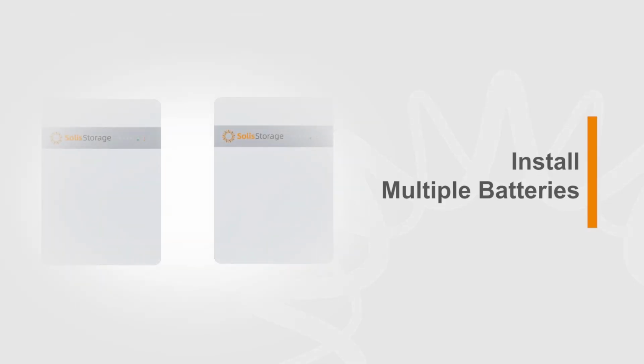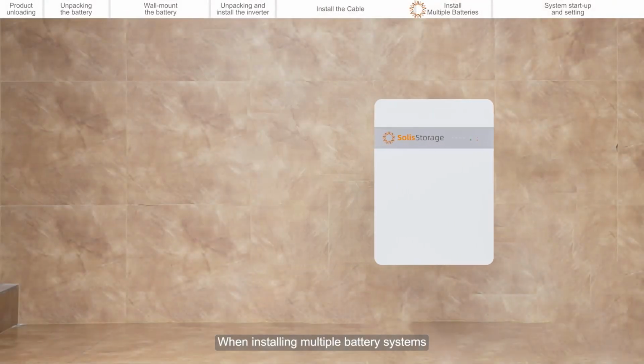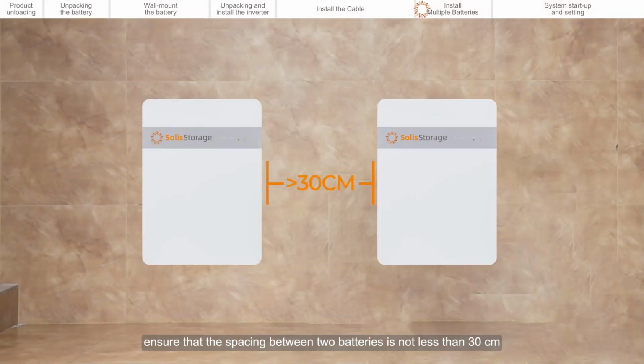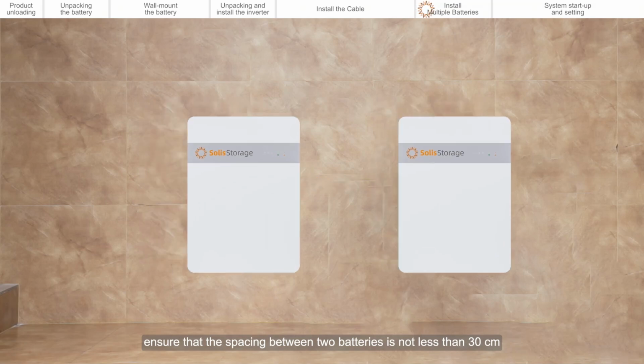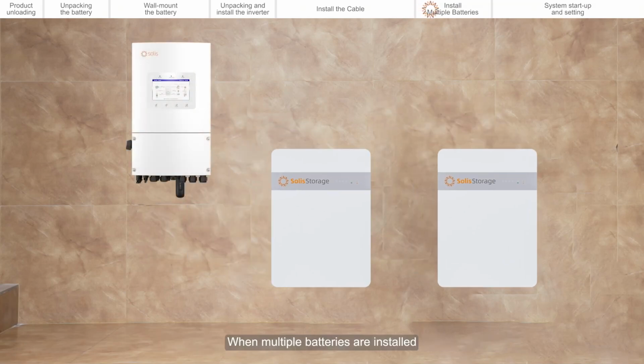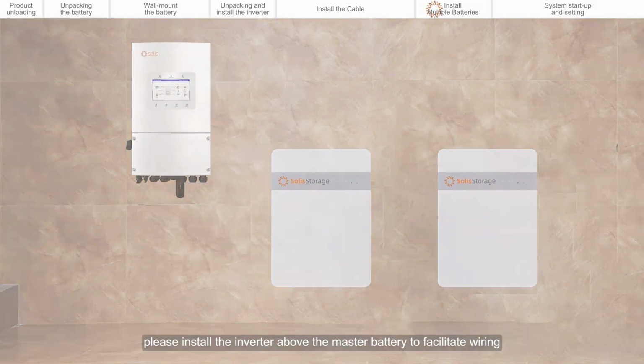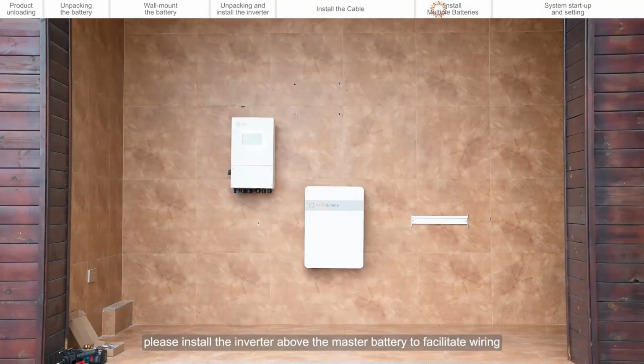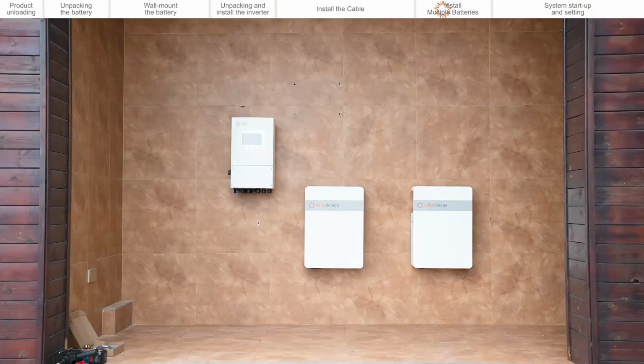Install multiple batteries. When installing multiple battery systems, ensure that the spacing between 2 batteries is not less than 30 centimeters. When multiple batteries are installed, please install the inverter above the master battery to facilitate wiring.